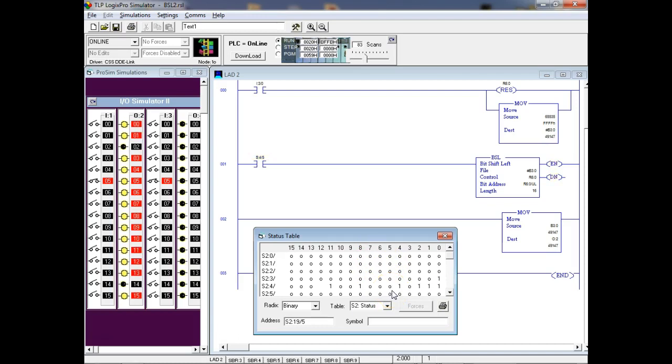And you can see every time it comes 1, this guy right here energizes, and every time it comes 0, it energizes for me. So what I'm doing is setting up timing, I'm letting the PLC do it for me. Instead of me trying to cross couple these timers, the PLC's got this free running clock in there, and I can just pick what bit I want to use. The slower I want it, the further I move up in these bits; the faster I want it, I use this bit right here. This bit right here would be extremely fast, right?